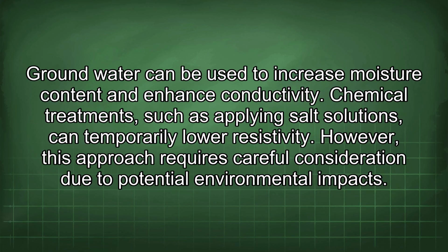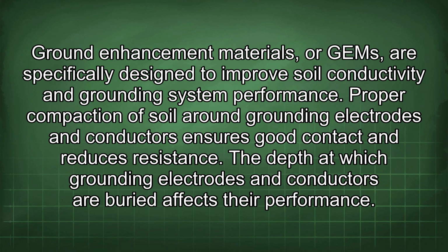Groundwater can be used to increase moisture content and enhance conductivity. Chemical treatments, such as applying salt solutions, can temporarily lower resistivity. However, this approach requires careful consideration due to potential environmental impacts. Ground enhancement materials, or GEMS, are specifically designed to improve soil conductivity and grounding system performance. Proper compaction of soil around grounding electrodes and conductors ensures good contact and reduces resistance.